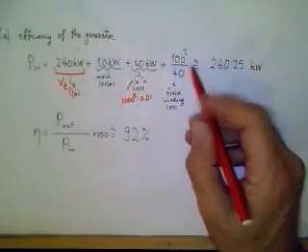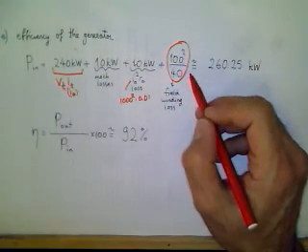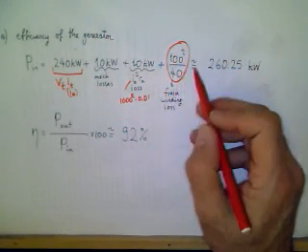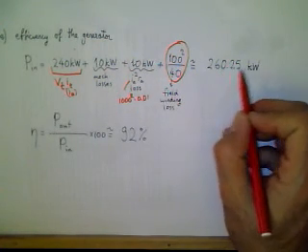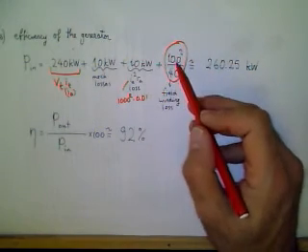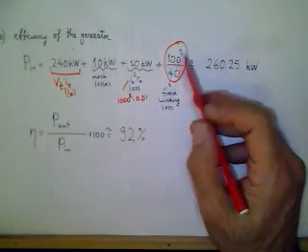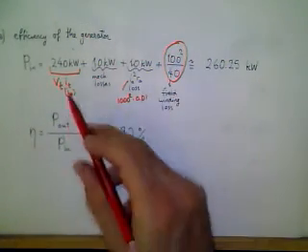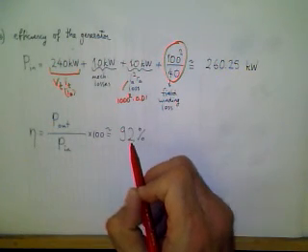And this term is the power loss at the field winding, so field voltage over the total resistance in the field. That ends up at 260.25 kilowatts. Sometimes you may neglect this, but in my opinion we have to also include it, because that power is lost in the field by some heating loss, etc. So the efficiency is 240 kilowatts over 260.25, roughly 92%.